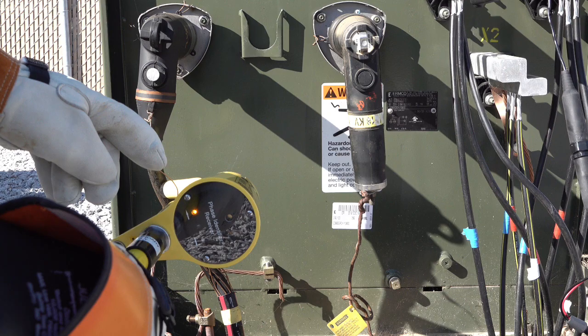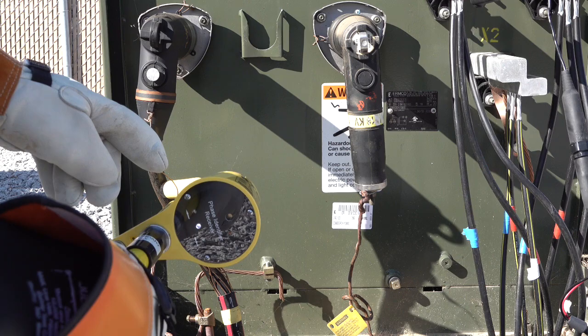Also notice where the STRCV probe tip is located. It must be located above the concentric, rest firmly on the primary cable in the concave, perpendicular to the primary cable. If this was the last primary pad mount in series with other pad mount transformers, what you would notice in every succeeding pad mount transformer going back to the riser pole is the same light sequence on the STRCV. In other words, every H1A primary bushing cable would have a light pointing up going back to the ST800, and every H1B primary bushing cable would have the light pointing down. This would indicate which primary is feeding the pad mount and which primary is feeding out of the pad mount.